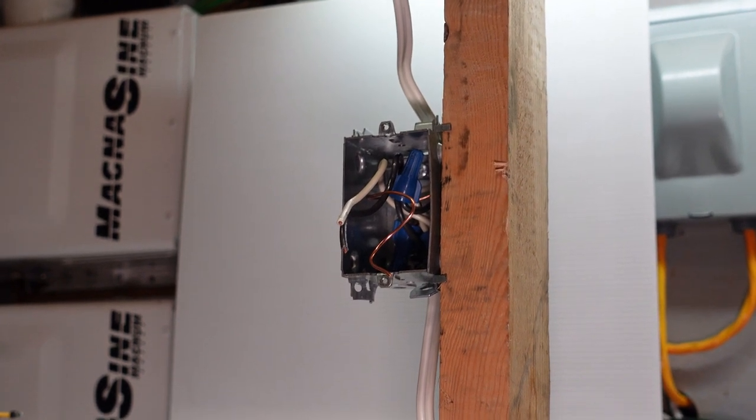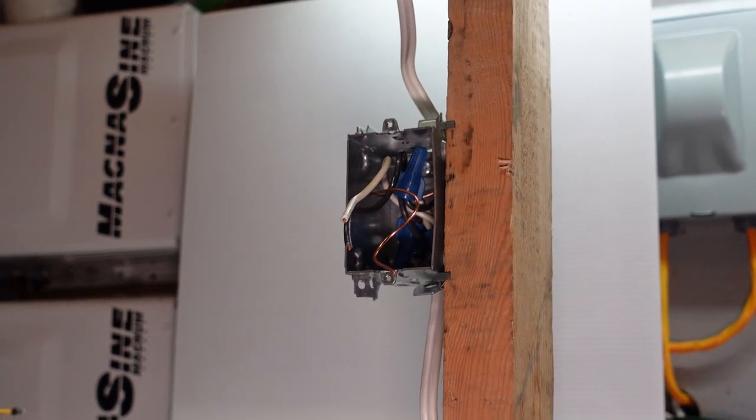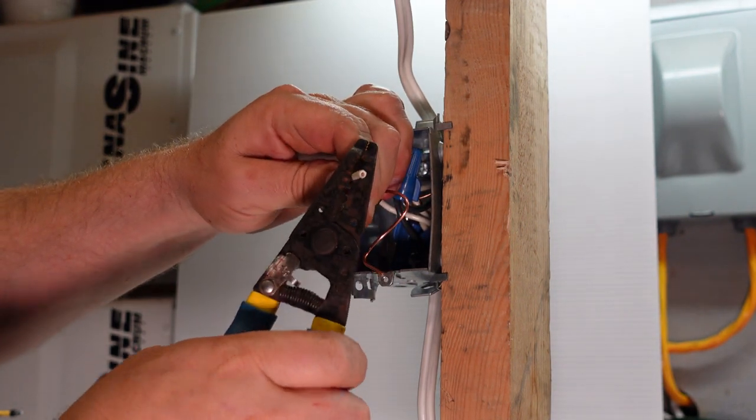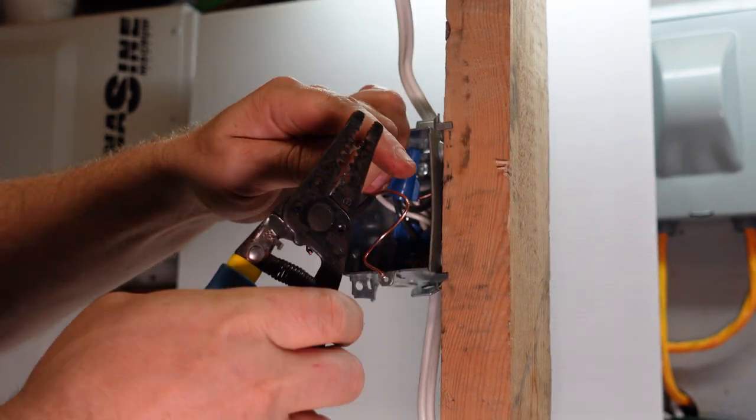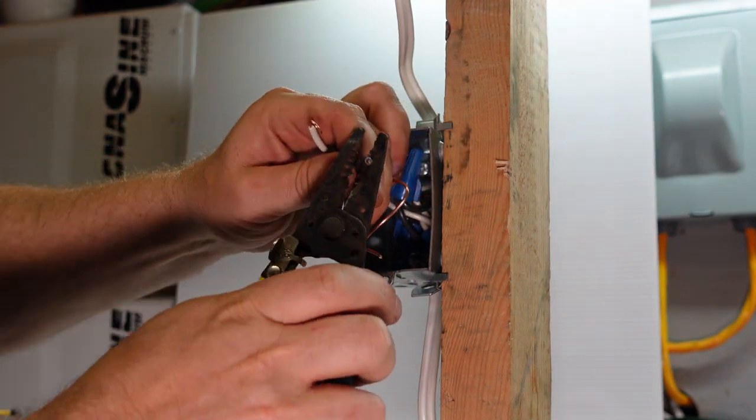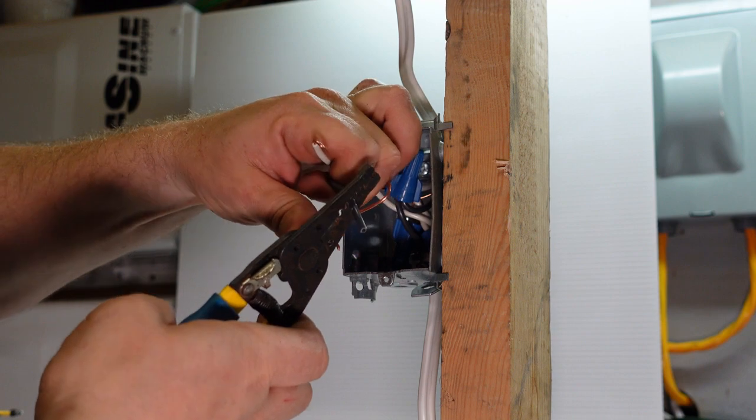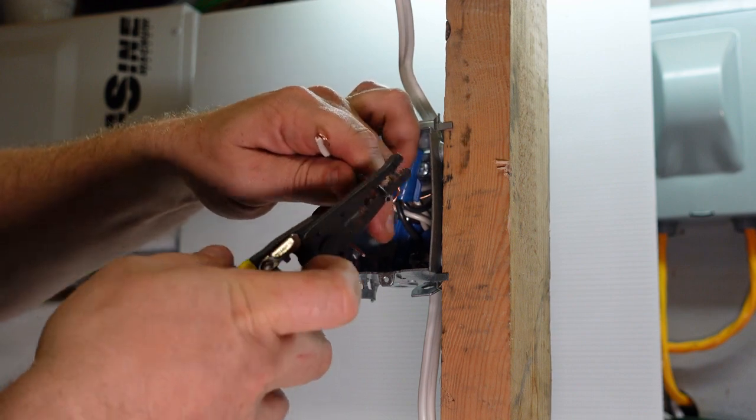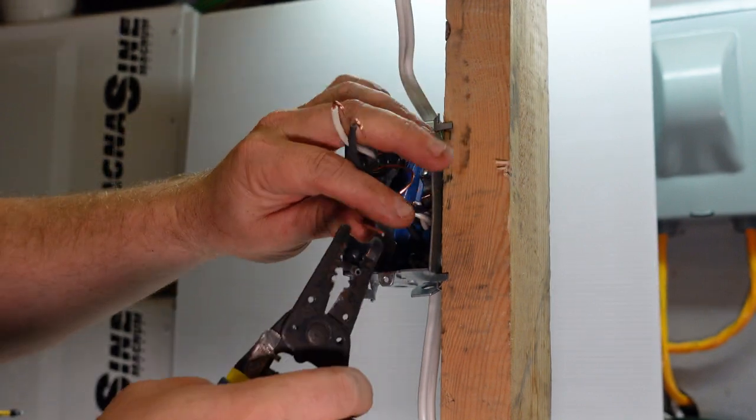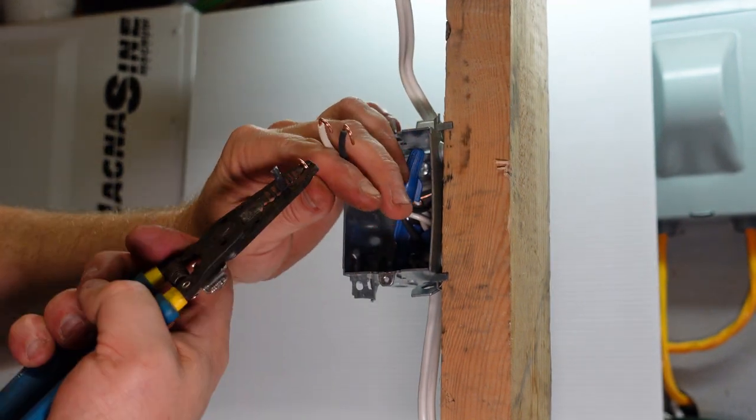Grab one off the bench here and we are going to re-strip these wires with an actual pair of strippers. We're gonna strip them back about three quarters of an inch and we're gonna put hooks on them in a clockwise motion, not counterclockwise, and we're gonna do that the same with the bare grounding conductor.